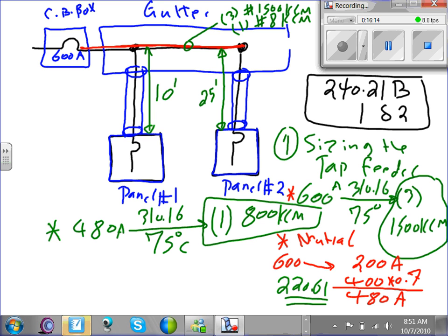Why did you say THHN? I thought it was THHW, in the 90 column right here. THHW would be outside. If you're using THWN, you're going to use it outside. If you don't know where the feeder is located, the assumption is a dry location. So we use THHN. THHN exists under 75, and also under 90. And we know why we don't go to the 90. 90 is only for derating.